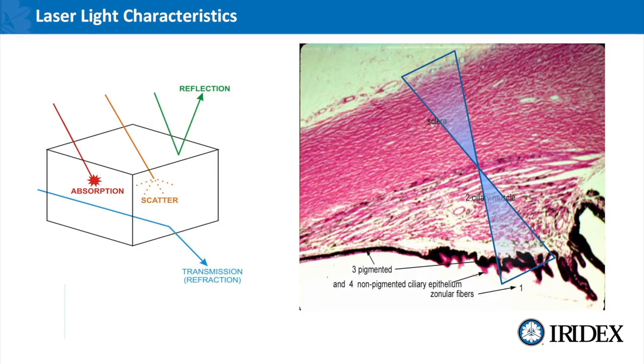All of these lasers operate on the basic physics of light and photon dispersement — you're going to get reflection, absorption and transmission of those photons from this beam path. Scatter is actually a very complex version of reflection. If you look at the target tissue, which is conjunctiva through sclera into the ciliary body, that will be your beam path for how you're treating with the MP3 device. You can see kind of an inverted cone application of how that laser path of photons is dispersed throughout the beam. This is not a 50 micron or 100 micron spot laser — this is a cloud of photons being delivered to the tissue and that cloud can be up to a millimeter and a half wide at its widest points.